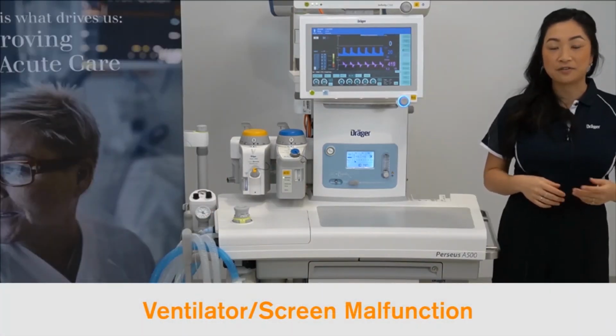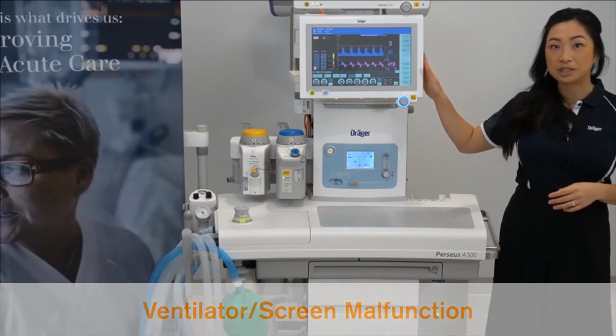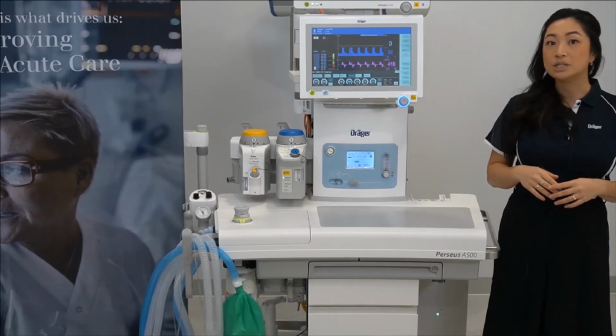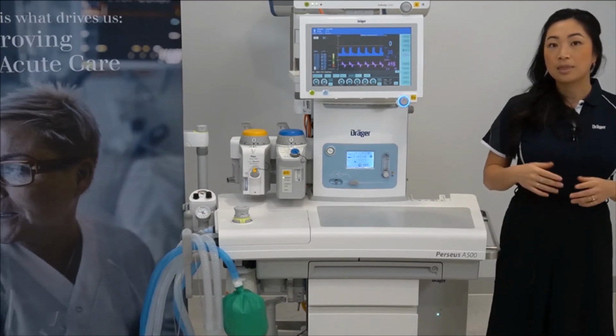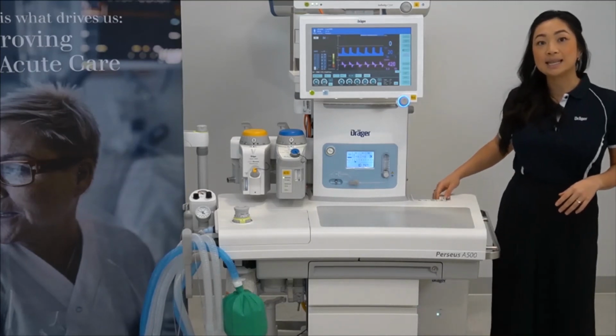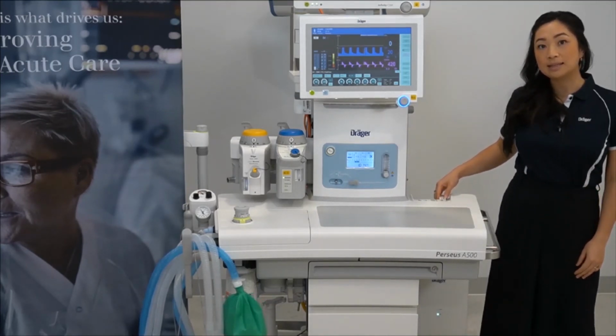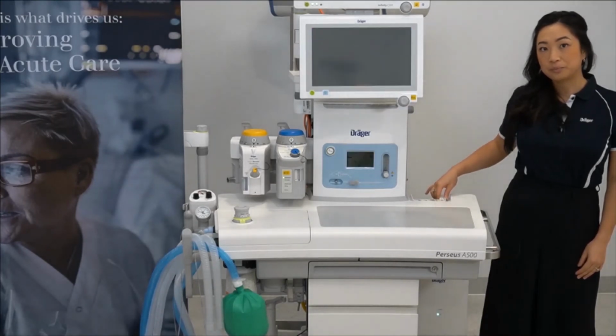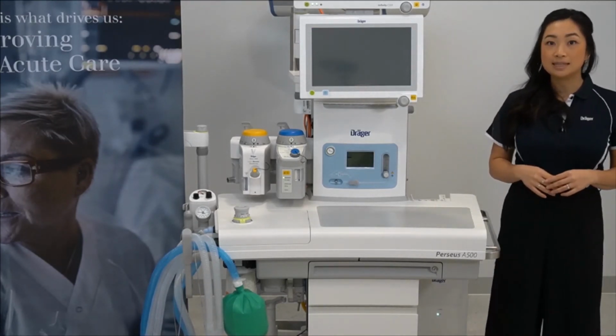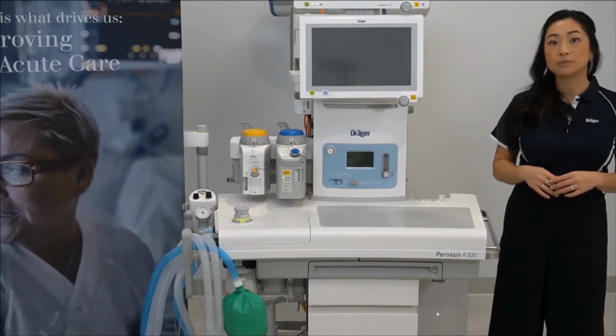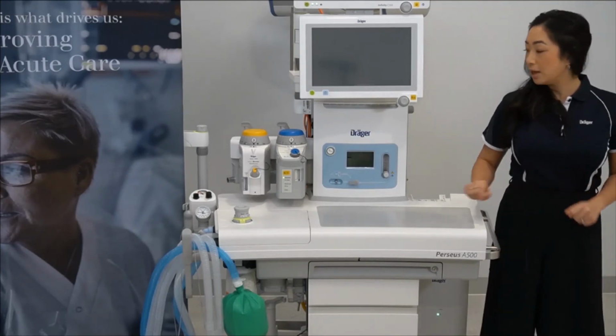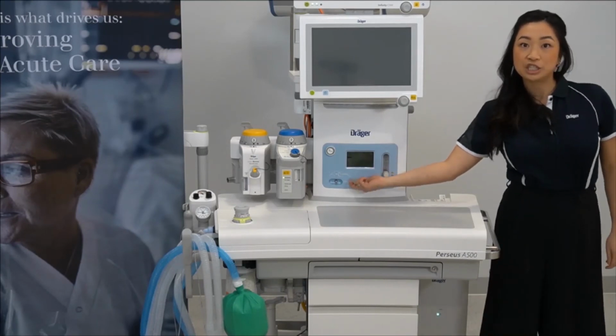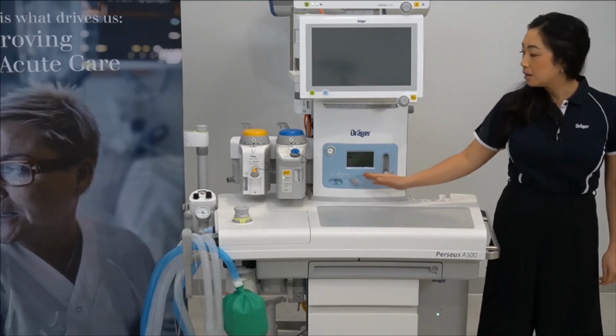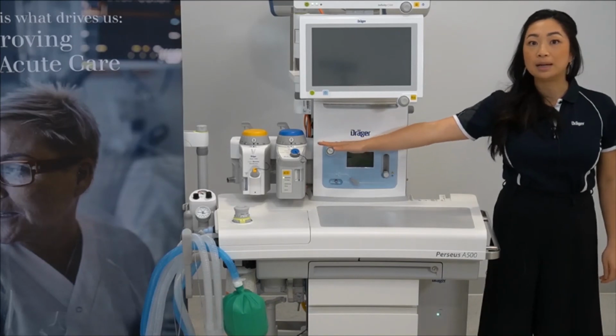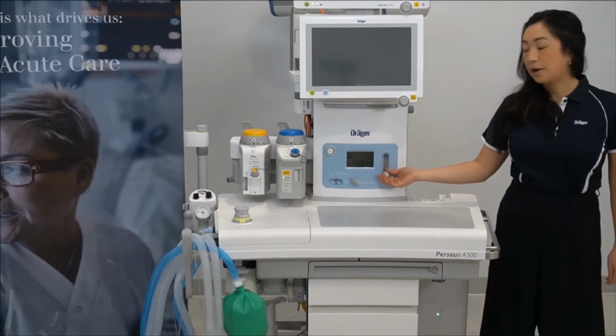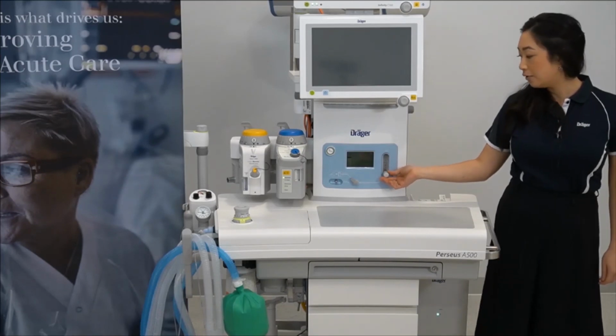In the event of a ventilator failure or a screen malfunction, you will not have the ability to control the ventilator. Therefore, you would then need to access the main power switch for the device and switch that off. This switch is typically used for the long-term storage of the device. Then, you would set your oxygen switch to add O2, which will mean the oxygen will flow through your back bar into the breathing circuit, and open up your flow control valve to your desired flow.